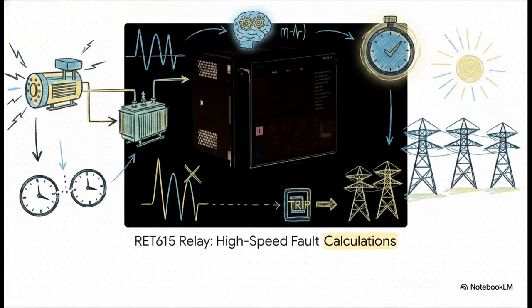Now, because we are dealing with two totally distinct sources, the static grid on one side and a spinning machine on the other, this differential protection has to be incredibly sensitive, yet perfectly stable across both current sources simultaneously to prevent a false trip. It requires highly tuned millisecond-level calculations. If your system is even slightly misaligned or incorrectly interprets an external surge, you could trigger a nuisance trip. But if it works properly, it's a remarkably effective safeguard capable of catching those internal imbalances way before they have a chance to escalate into total mechanical ruin.